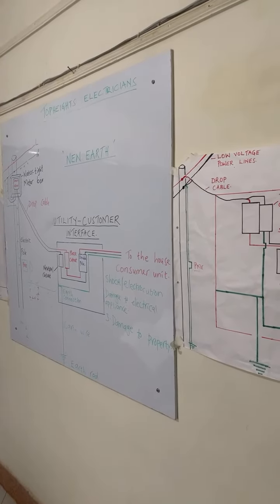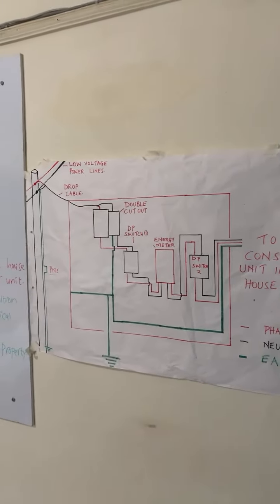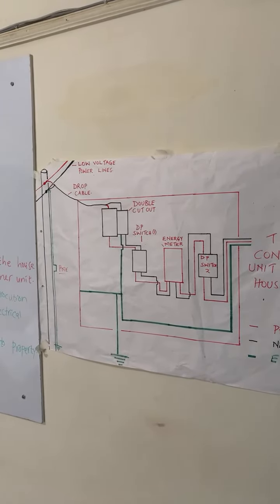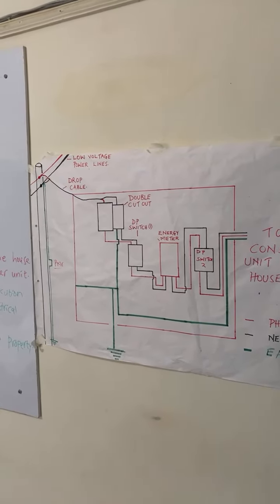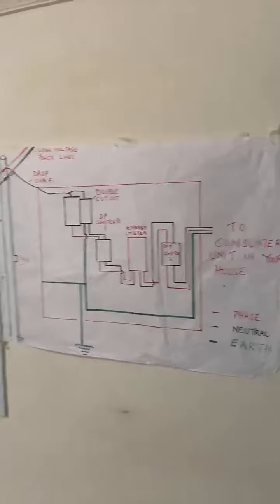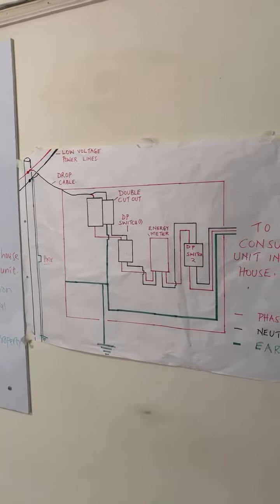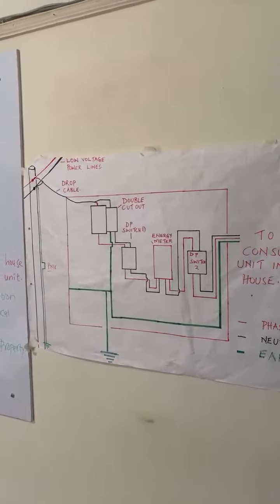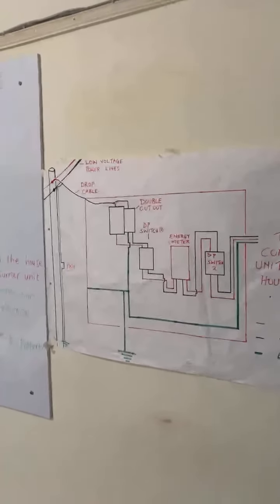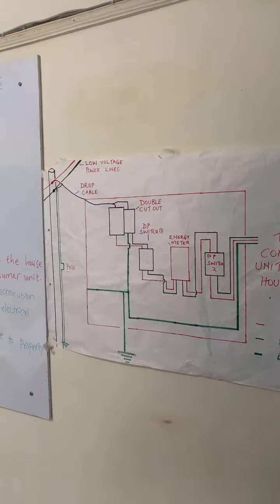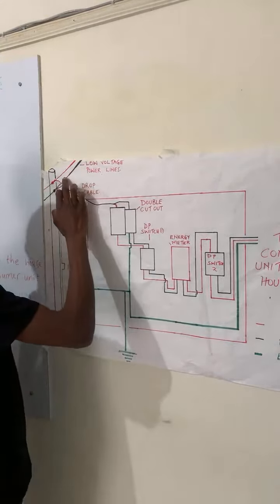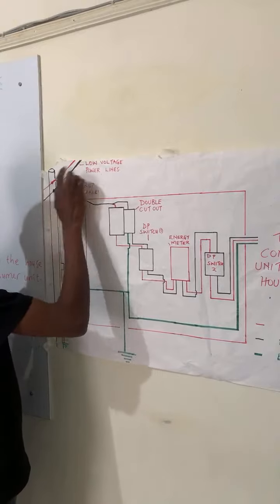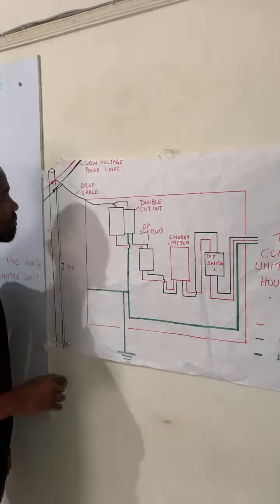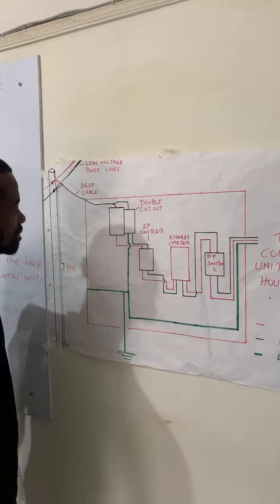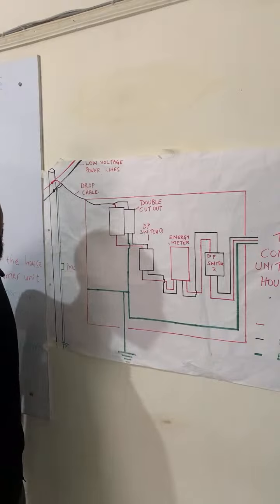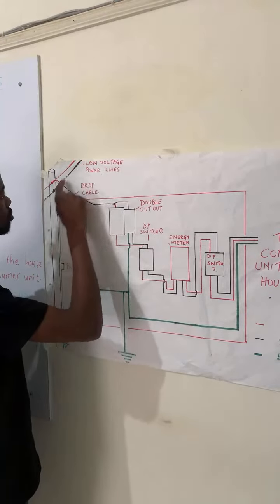First of all, to introduce what we are used to here. This is the meter box, and I'm going to share exactly the flow of electricity all the way to the consumer unit. Now, from the pole, as we can see, we have what we refer to as the feed or the national grid here. We have the phase, which is the live connection, marked red. For this case, I'm assuming the color code I'm using now in my country, and I've tapped from the red phase. So from that single phase, I also have the neutral.